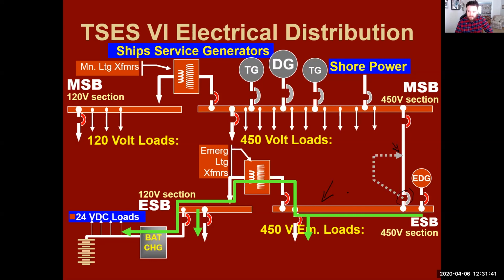But some vessels will have their emergency generator used as their harbor generator. On my last ship, we used it that way. Every time we pulled into the pier, we would shut down our main generators and basically just run on our emergency. So does that mean we're walking around with only emergency loads running? Does it mean I can't take a shower because the light in my shower isn't on the emergency bus? What do we do? What is an engineer to do in this situation? Is there anything, or do you just hope?